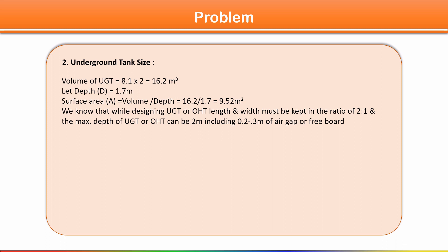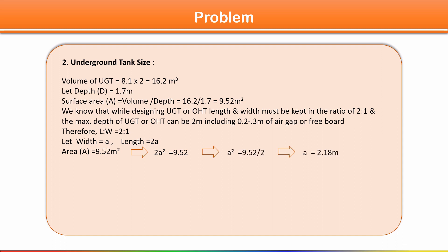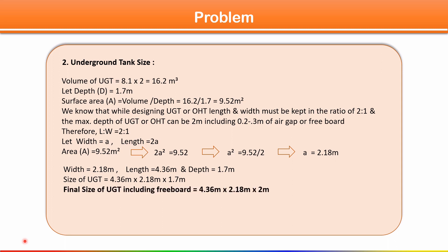For UGT, length to width ratio is maintained at 2:1. Let width = a, length = 2a. Area = 2a² = 9.52, so a² = 4.76, giving a = 2.18 meters. Therefore width = 2.18 m and length = 2 × 2.18 = 4.36 meters. This is not the final size — freeboard must be added.